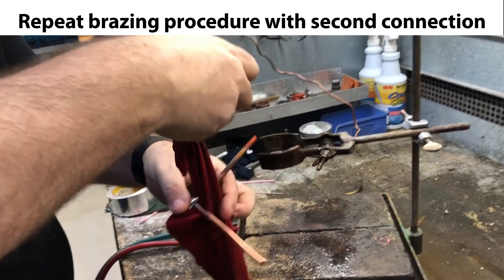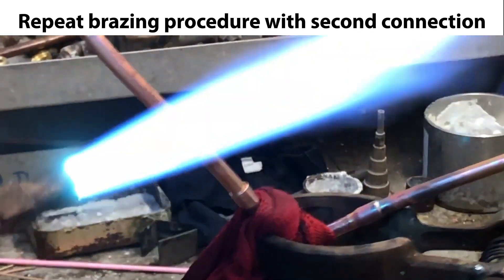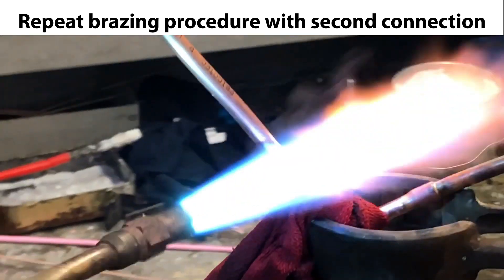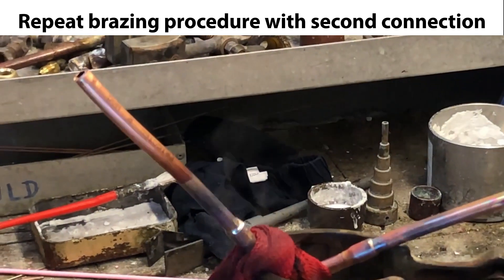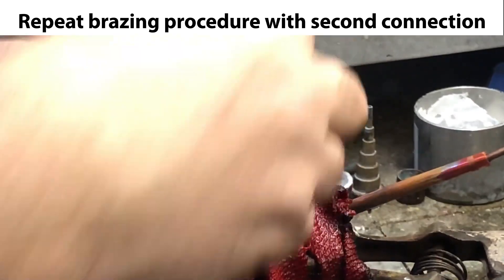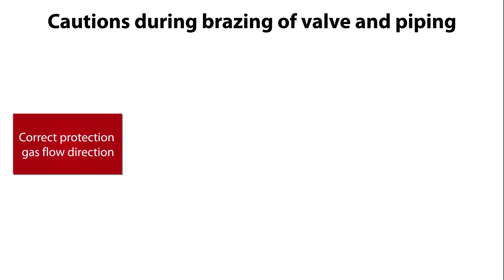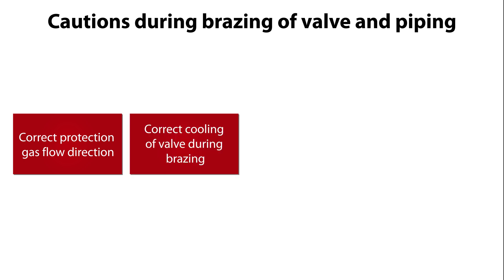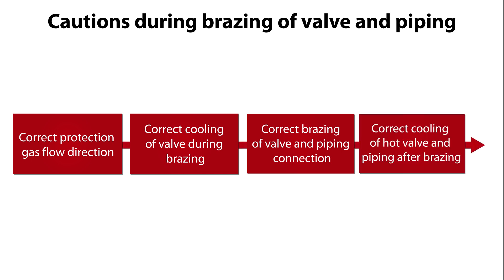We're now ready to repeat the whole brazing procedure for the second connection between valve and piping, as seen shortly in the following sequences. For this second brazing, it is very important to pay special attention to correct protection gas flow direction, correct cooling of the valve during brazing, correct brazing of the valve and piping connection, and correct cooling of the hot valve and piping after the brazing.